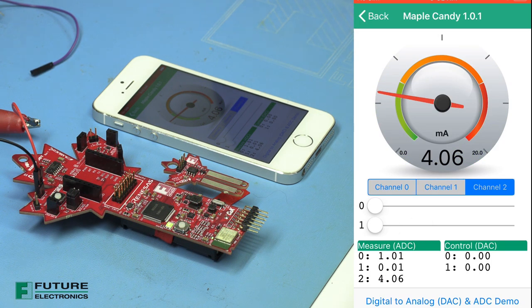For all of you with industrial clients, here's a 4 to 20 milliamp input. As you can see, it reads 4 milliamps and goes up all the way to 20 milliamps.